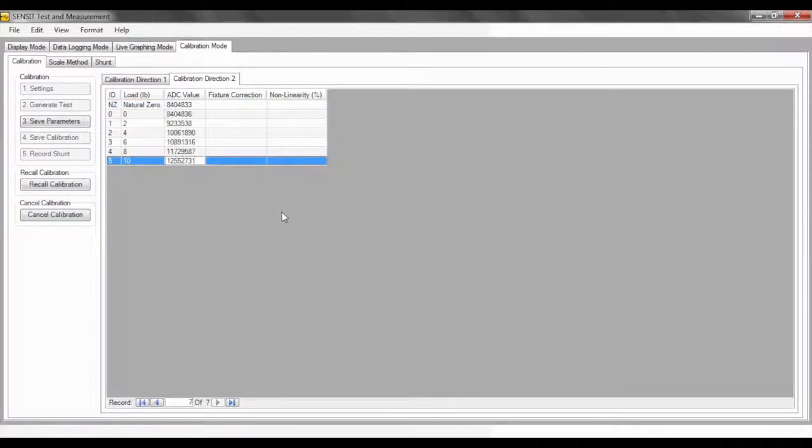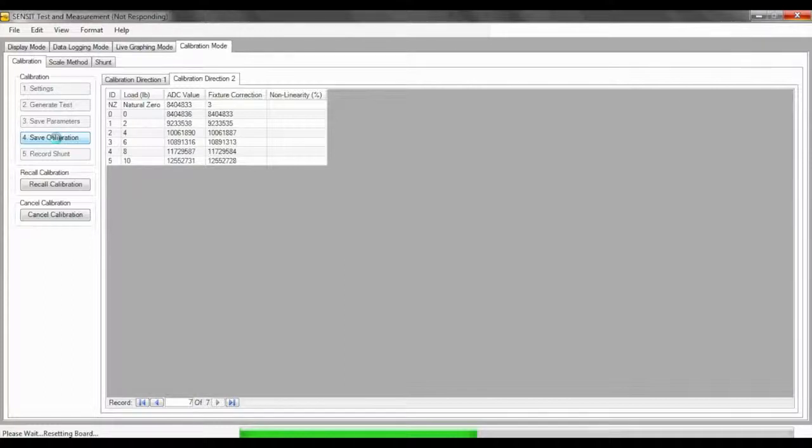After completing and saving your recorded ADC values, click the number 3 step, Save Parameters, also the number 4 step, Save Calibration. Below you can see a Shunt button. Shunt is used to simulate a load on a load cell using an internal resistor within the USB instrument. Because there is no access to the shunt resistor in the USB instrument, the shunt value may result in a simulated load over the sensor's capacity. Shunt can be used to evaluate the sensor over time and to verify the connection from the computer to the instrument and to the sensor.